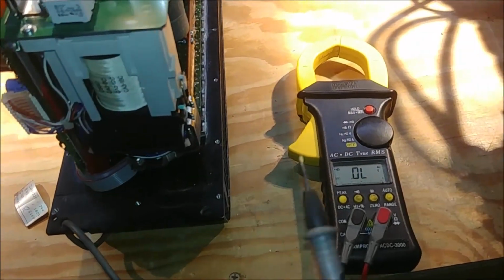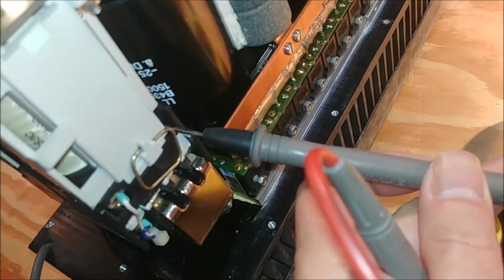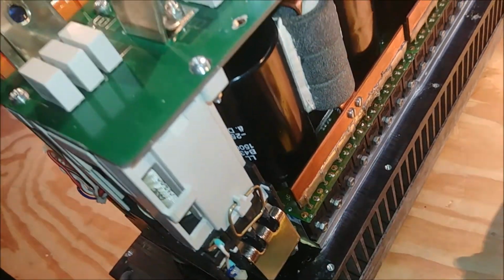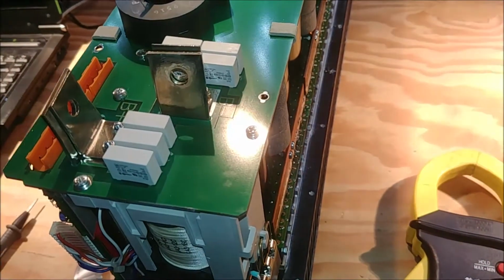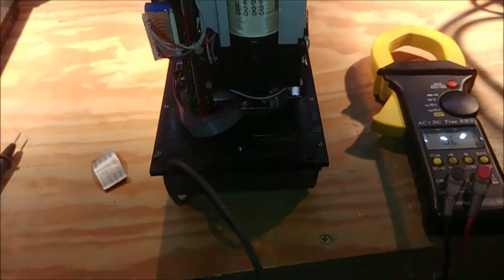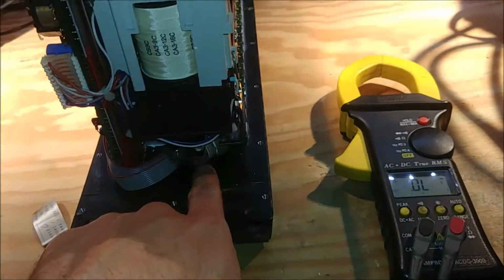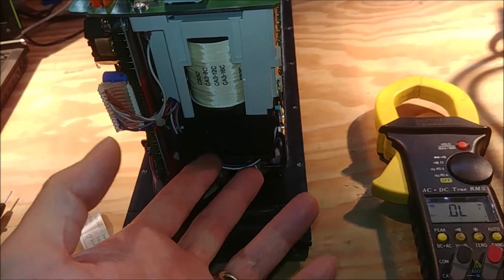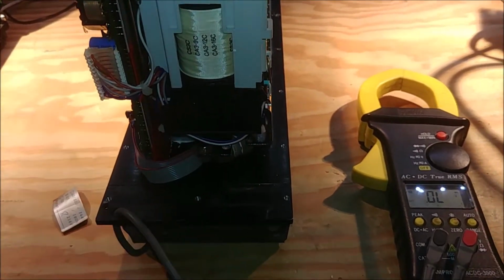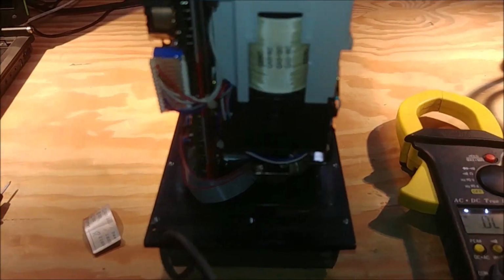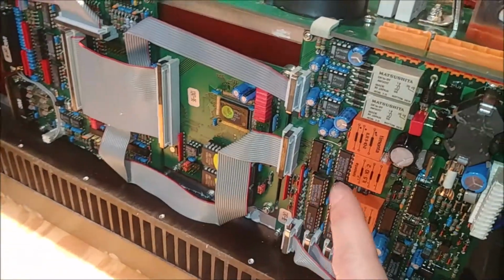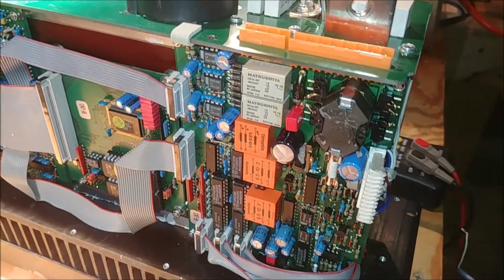The other one's a little harder to get on because you have to go inside here to the bus bar that goes up that way. But I think all that's wrong is we've popped our main fuse. We might have a bad - well, the contactor needs to be replaced because it's melted. Replace the fuse. I don't know if I have another power supply board.